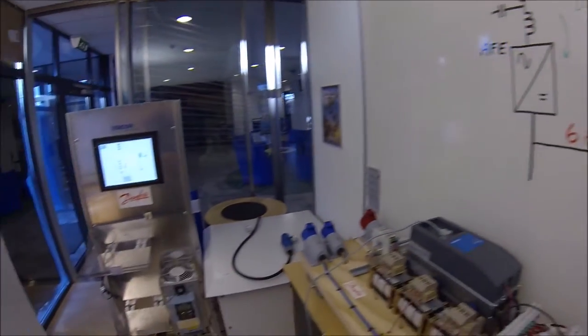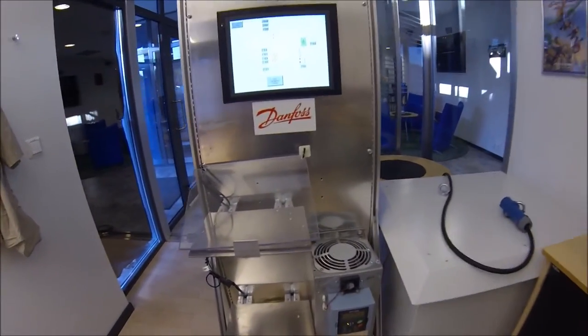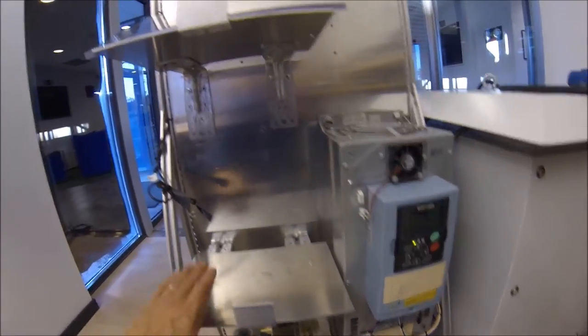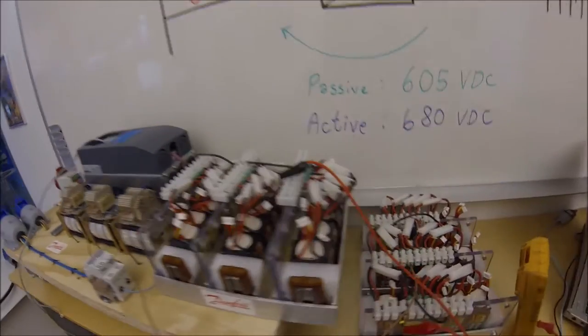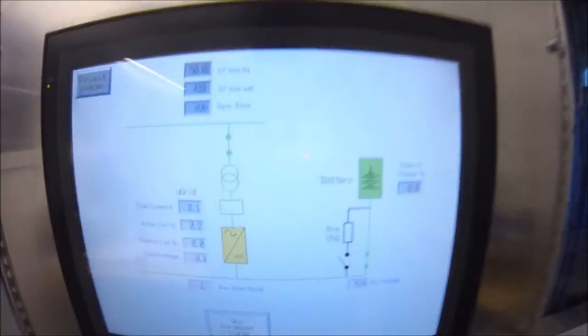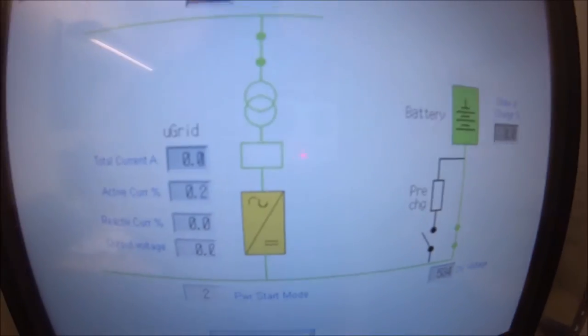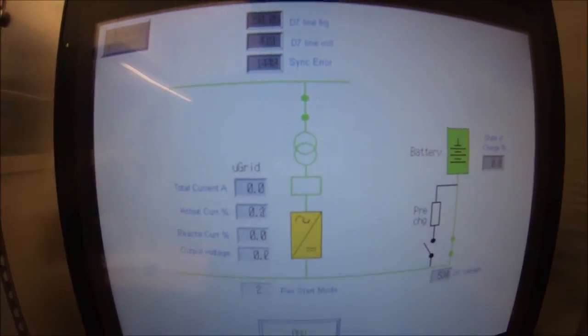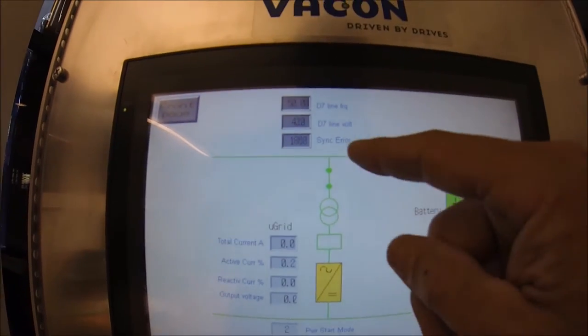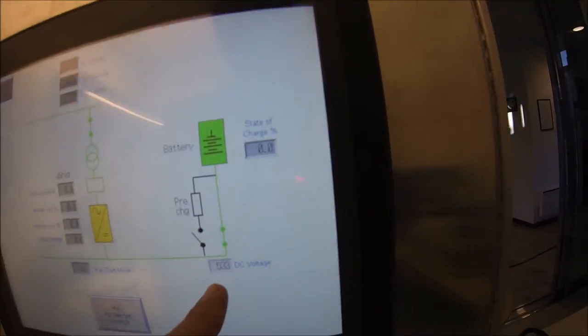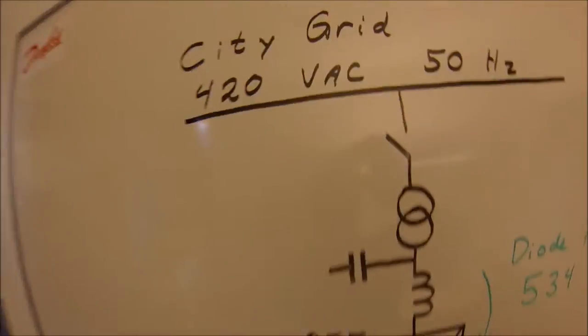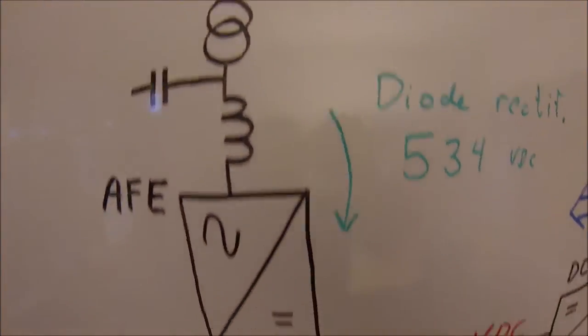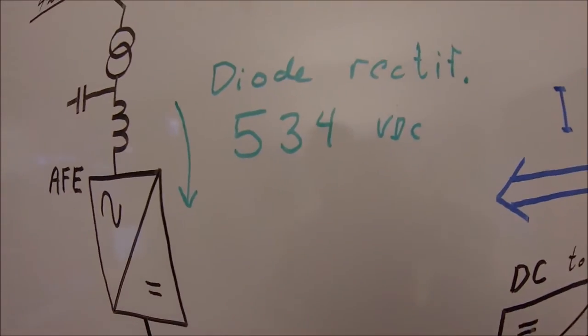If we look at our simulator, the hardware is exactly the same as the microgrid. We have removed the batteries. The batteries are now over here to this side of the DC to DC converter. The active front end has been pre-charged and is connected to the city. So it means that the diode rectifier mode now will produce 534 volts. So this is the 420 volt AC diode rectified to 534.